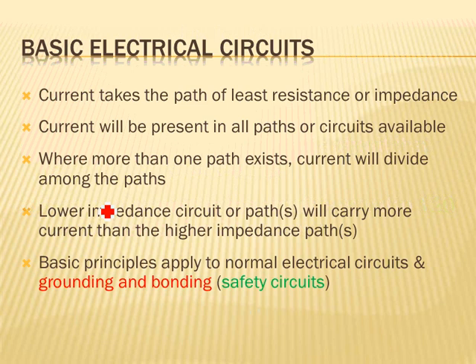I'm going to emphasize the grounding principle applies, like I said, to normal and abnormal operation, which is grounding and bonding. It's called the safety circuit. All the green stuff that I showed you guys, all the grounding and bonding, is part of the safety circuit. For example, look at that. Current takes the path of least resistance. Current will be present in all paths of the circuit. Where more than one path exists, current will divide. This is normal operation of a circuit, right? And at the same time, abnormal operation: a low impedance circuit or path will carry more current.